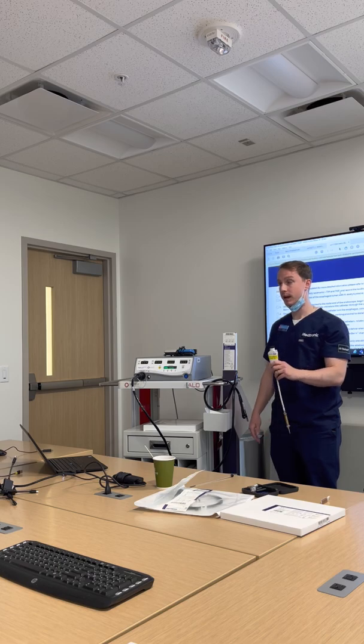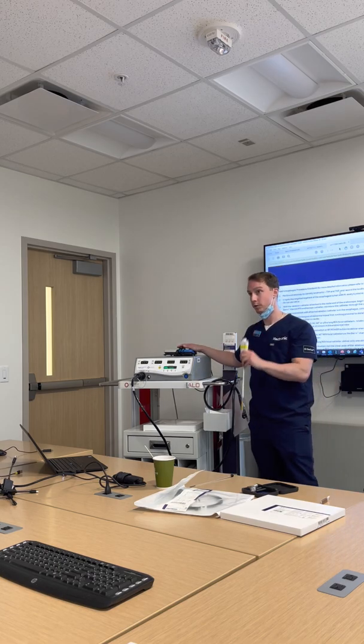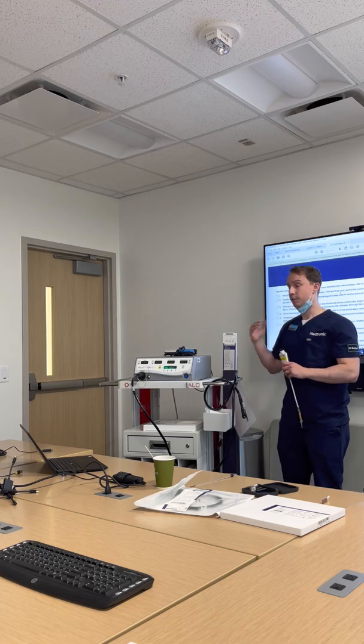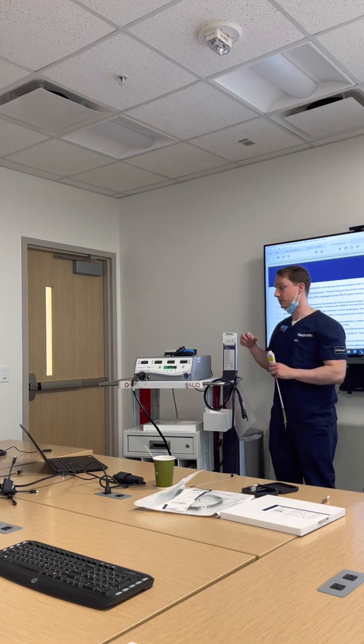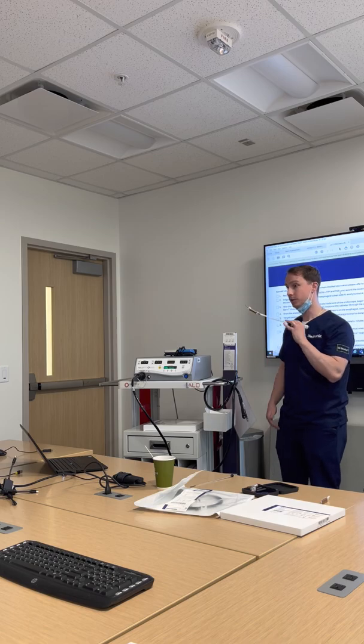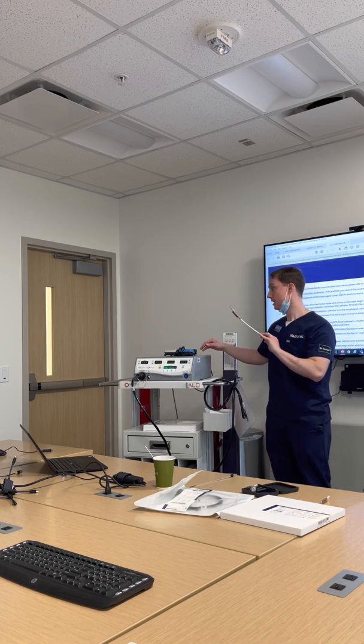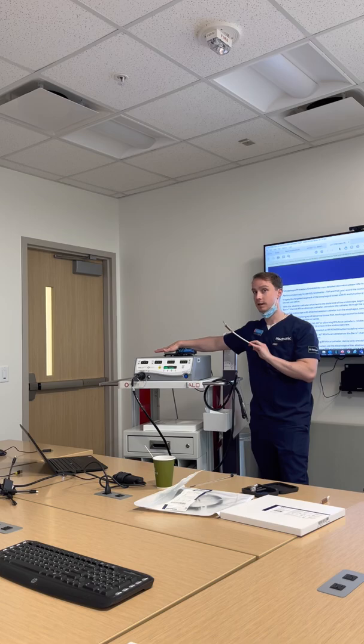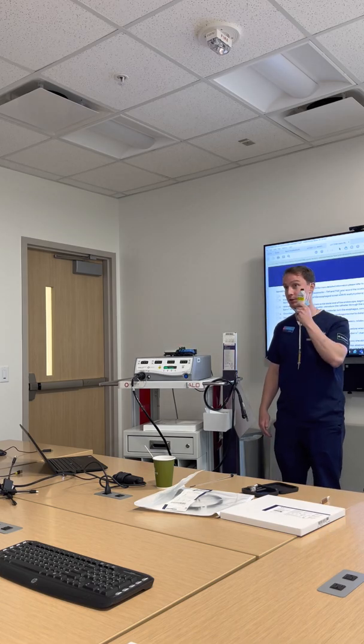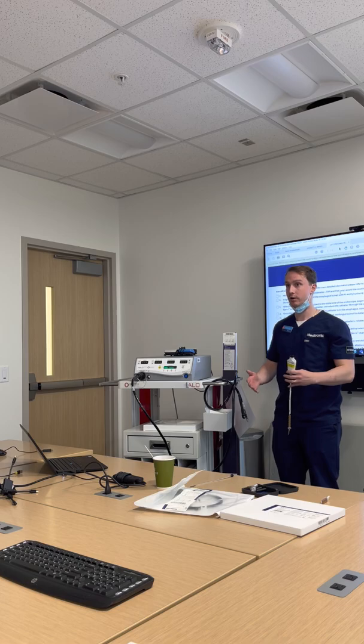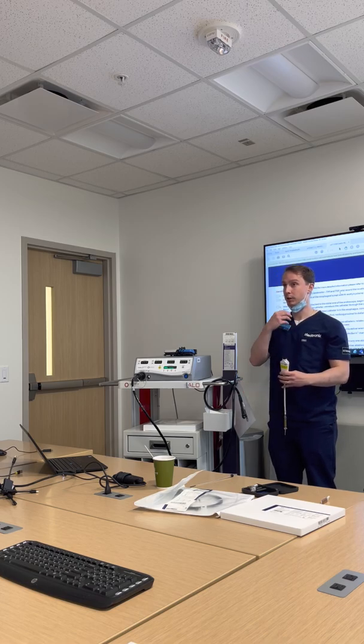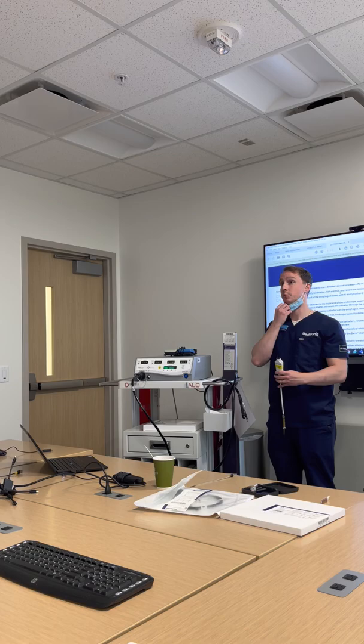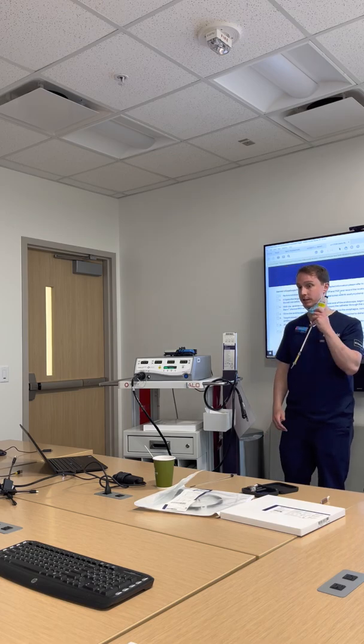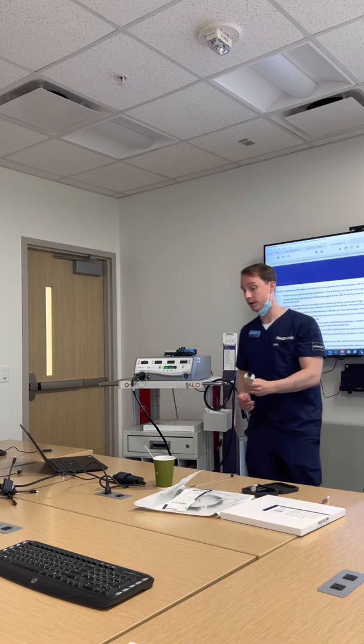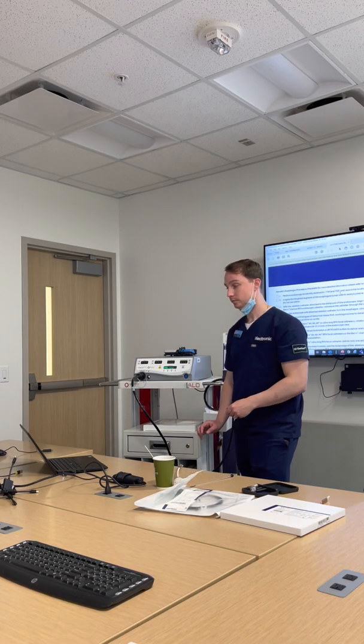We do not want this thing connected to the system until we are fully in place. That's difficult sometimes because that becomes a part of our process, getting everything connected, then dropping it. The thing with the 360 Express especially is if we click auto inflate by accident, it will auto inflate whether we're in position or not. Not super detrimental in any regard if we're anywhere below the UES. If we're right by the UES and we start to inflate, that thing's potentially going to cause harm to the patient. So we want to make sure that it's down, it's in place, it's by our markings, and then we connect it to the system.